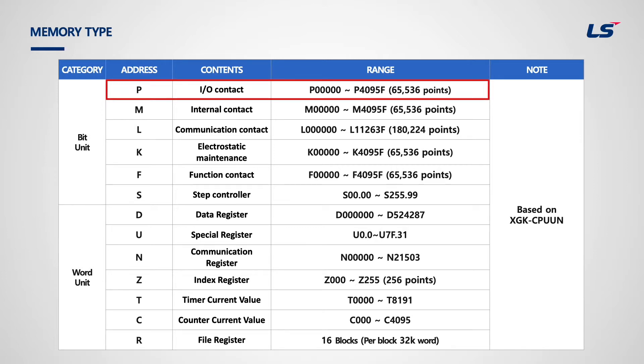P is an image area to save the state of input-output devices. After reading the input module state, it saves it in the corresponding P area and sends P area data saving the operation result to the output module. P0000's last zero is a bit, expressed in hexadecimal. There are 65,536 input-output points users can use based on XGK CPU UN. If input-output modules are installed, the number of input-output devices are allocated for those specific modules, and the rest can be used as internal memory.